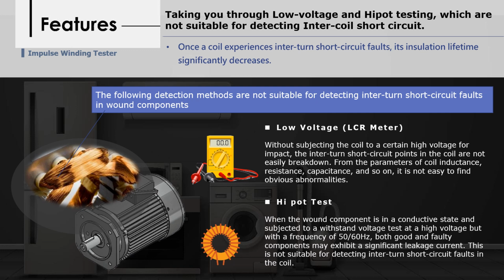For instance, if a portion of the coil in a motor winding is directly short-circuited, it cannot fulfill its inductance function. This leads to an asymmetrical magnetic field compared to a well-functioning motor. The remaining coil currents increase, causing vibration, high current, reduced output, and potential issues like noise, heating, or even burning over time. Traditional low voltage or hipot testing methods are not ideal for detecting layer-to-layer short circuits. Low voltage tests with a typical LCR meter may not reveal abnormalities due to the low testing voltage. On the other hand, a hipot tester, while using high voltage, operates at a frequency of 50 or 60 Hz that simulates a short circuit, and cannot detect layer-to-layer short circuit defects.